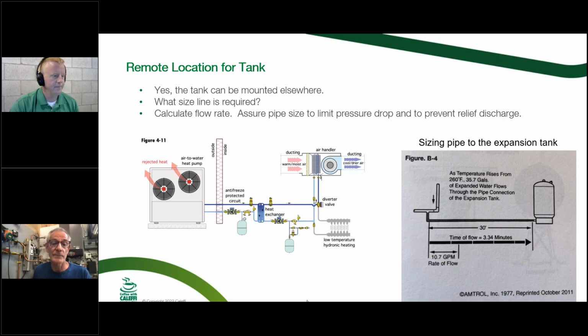We want that expansion tank in there also because as we cool the water, we can retract. The pressure is going to drop. So the same thing applies to geo. For years, the geo industry said, no, we don't need expansion tanks. The tubing can expand and contract and handle that type of thing. But really, on a chilled water system, there's a good reason to have them there.